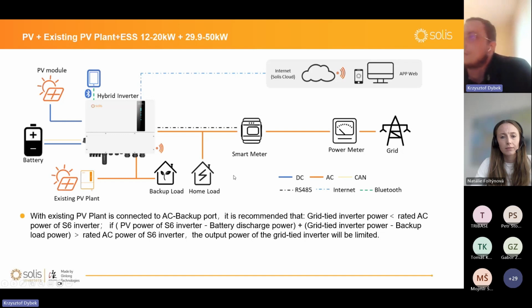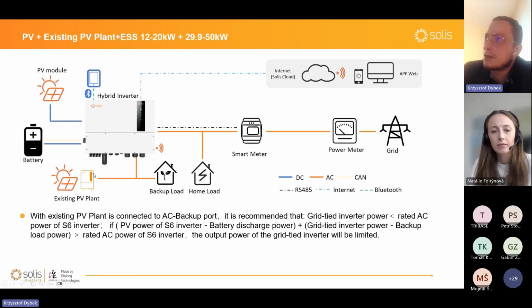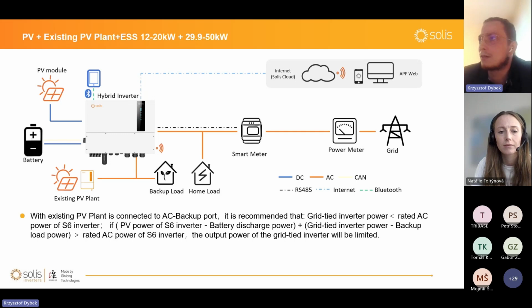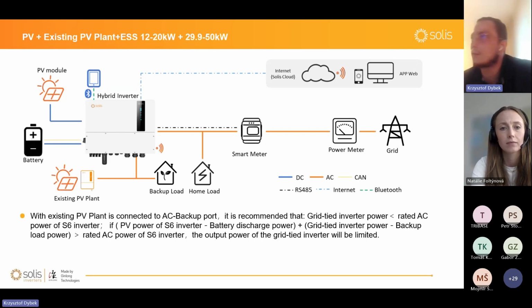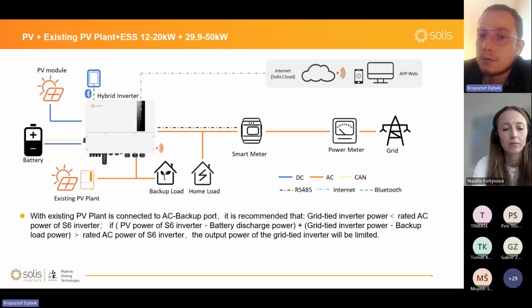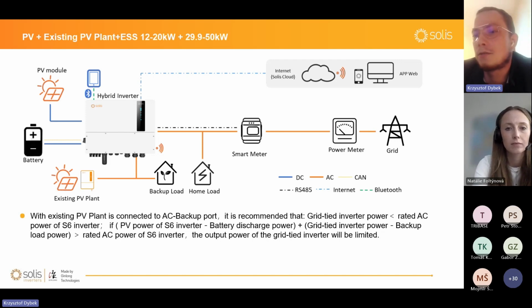Yeah, and we have a variation of it, let's say, to connect, instead of a diesel generator, an existing PV plant with any other grid-tied or hybrid inverter, doesn't matter, just any inverter. I can imagine that this scenario is not really common and will not be common, but we are ready for this as well. The purpose of it is to have a retrofit installation. When you already have a third-party grid-tied inverter and you don't want to remove it, this inverter can be connected to S6 and works like a generator. It starts production if needed, and ends production if the battery is charged and the load is covered. So the S6 hybrid inverter can simulate the operation logic of the power grid.